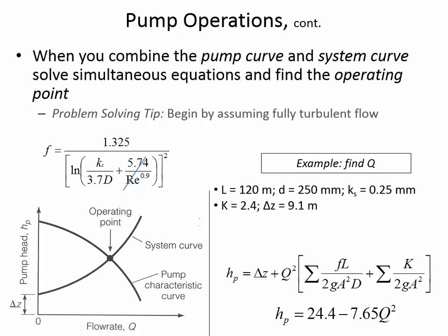So what we end up with is our system curve. Our system curve equation is H sub P is 9.1 plus 249.74 Q squared. Okay, so we have a system curve. It's the relationship between how much head is being added and what the flow rate through the pipe is going to be. Our problem-solving approach here is to set the system curve equal to the pump curve. So let's do that. System curve equals pump curve.